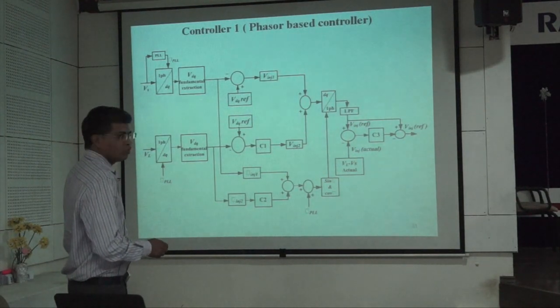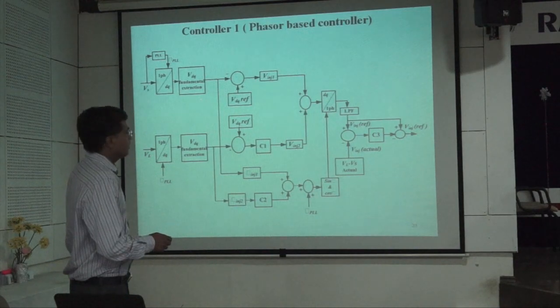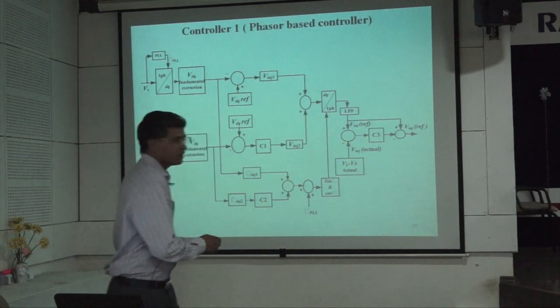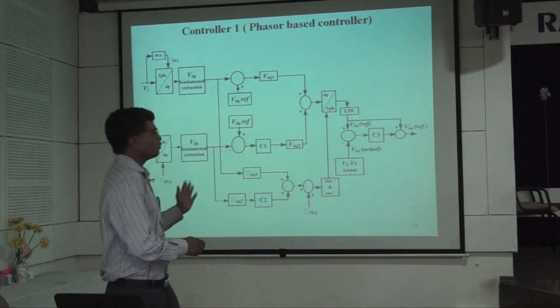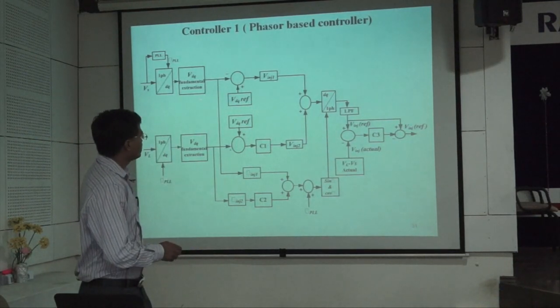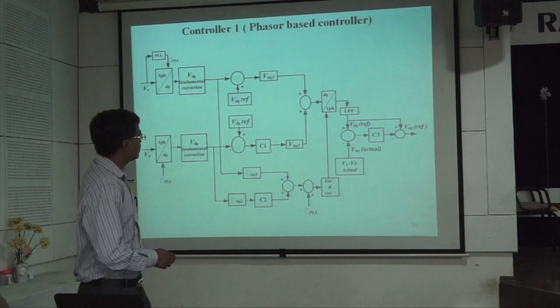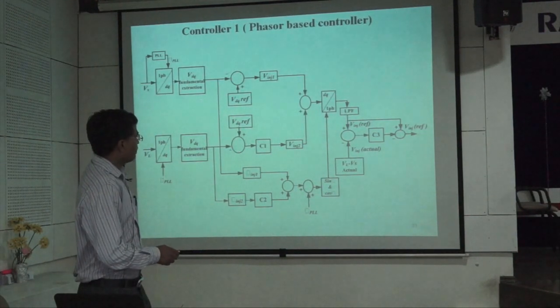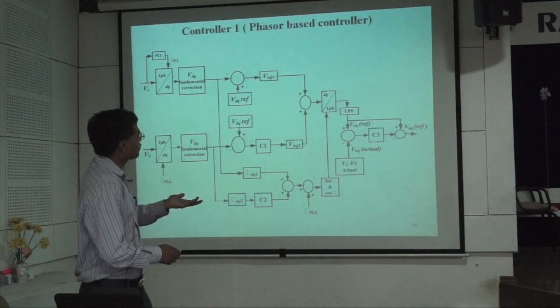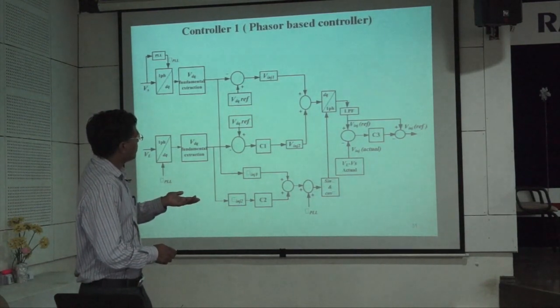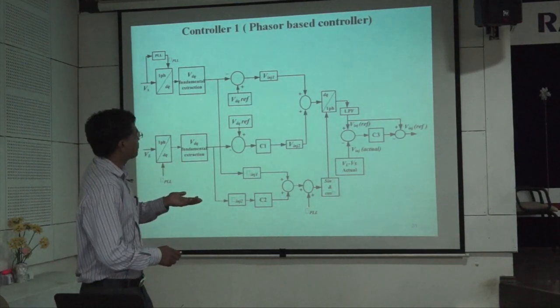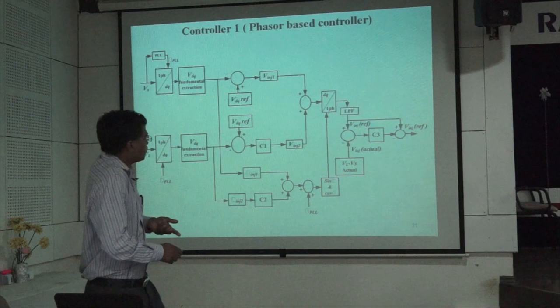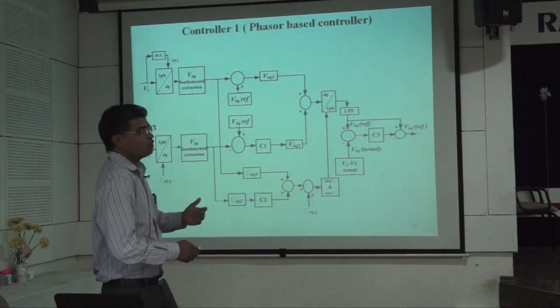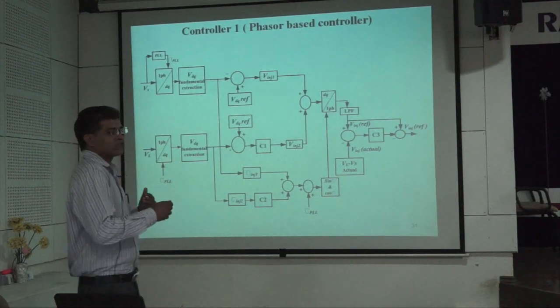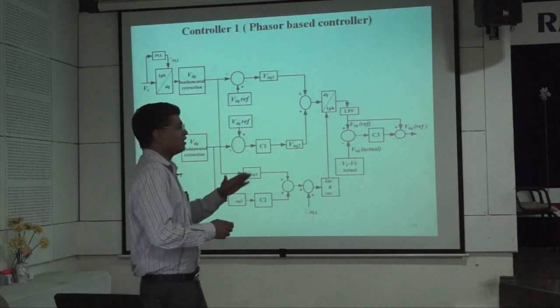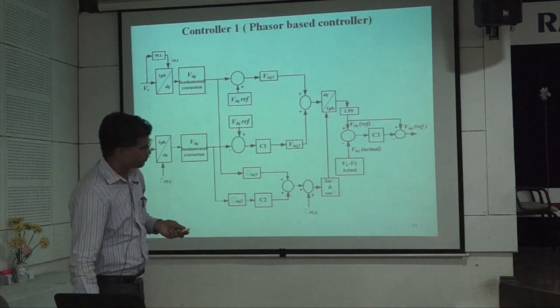Again, the injected voltage on the load side, both are added together. DQ components are converted into single phase components. The harmonics are removed by the LPF. The reference injected voltage is again compared with the actual injected voltage, and the error is minimized with the third PI controller. This third PI controller is implemented just to minimize the size of the transformer, to minimize the saturation in the injection transformer.